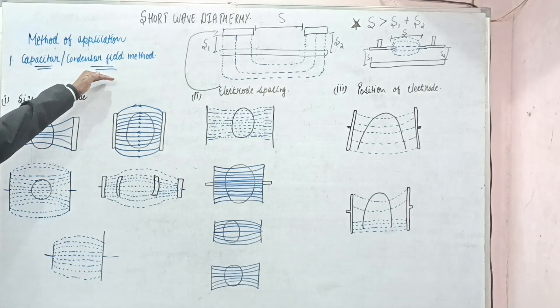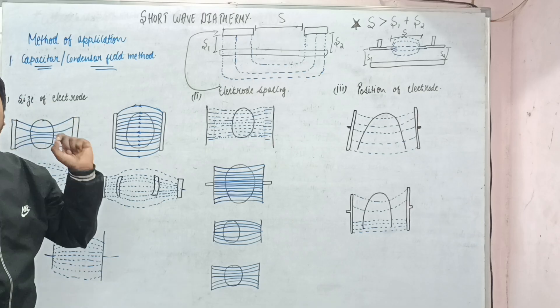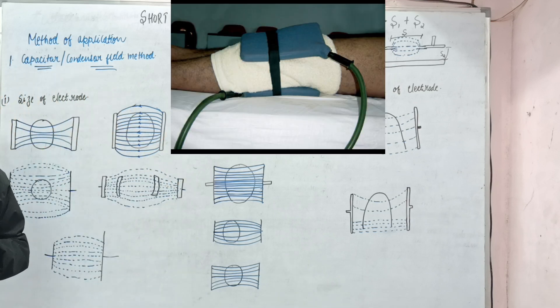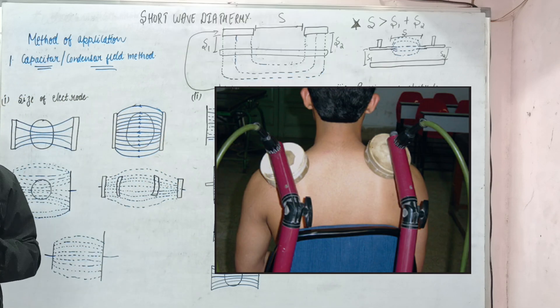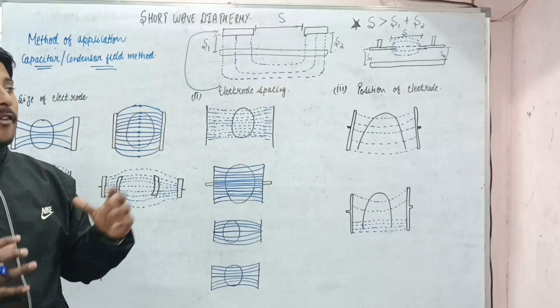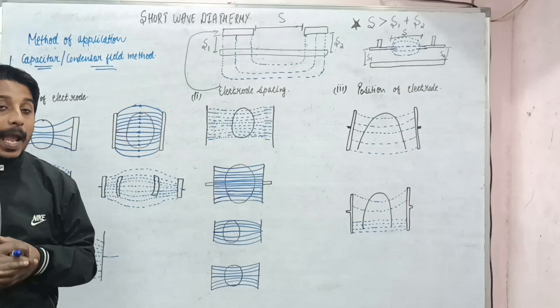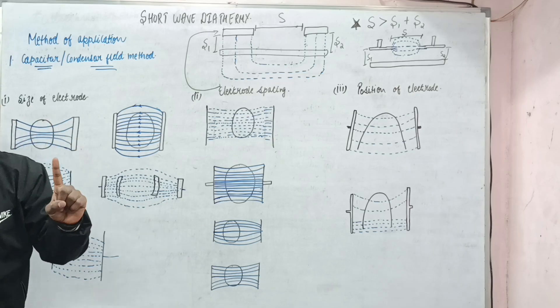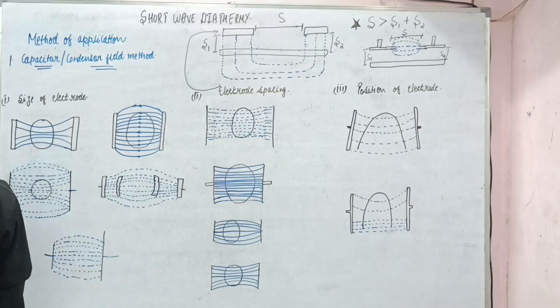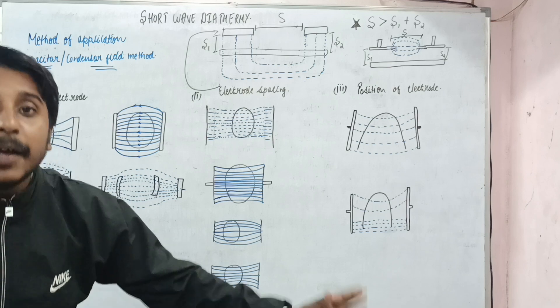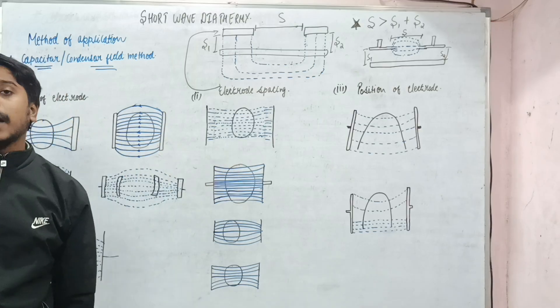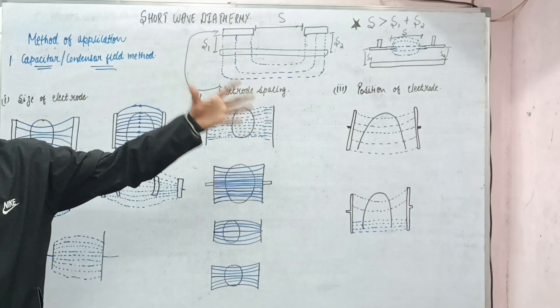First is the capacitor or condenser field method. Here we use electrodes for SWD application — either a pad electrode or a disc electrode. The pad electrode requires some separation done by a towel, while the disc electrode has air-layer spacing. The electric lines of force passing from these electrodes pass easily through material of high dielectric, and our body has a very high dielectric. So it is very easy for these lines of force to pass through the body and give a heating effect.